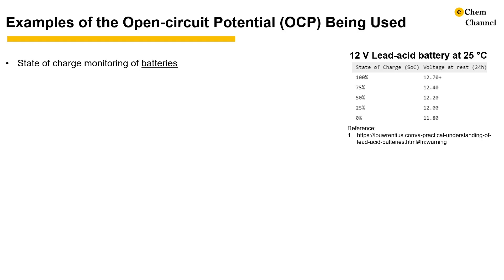In lead-acid batteries, people have used open-circuit potential measured at 25 degrees Celsius after 24 hours of resting to estimate the state of charge. An example is shown in the table on the right. This relationship can be tricky as it depends on the manufacturer and the aging condition.